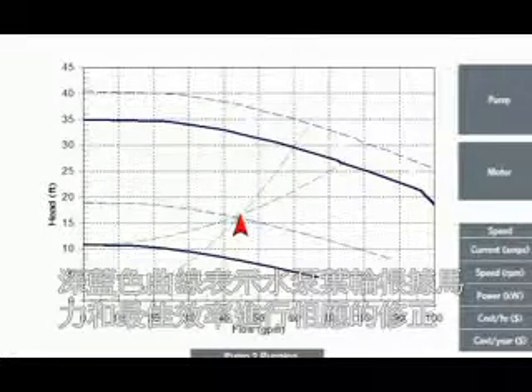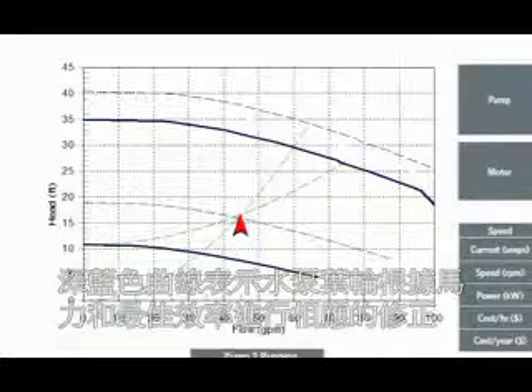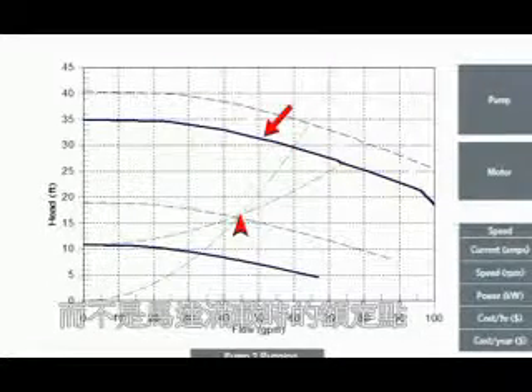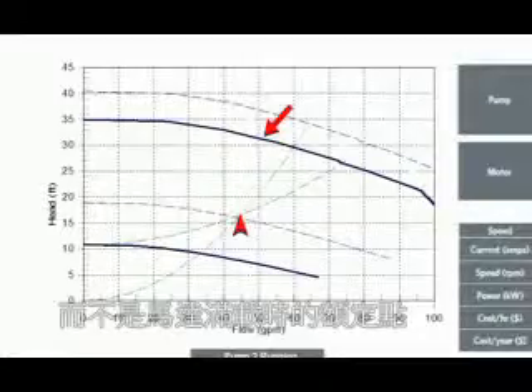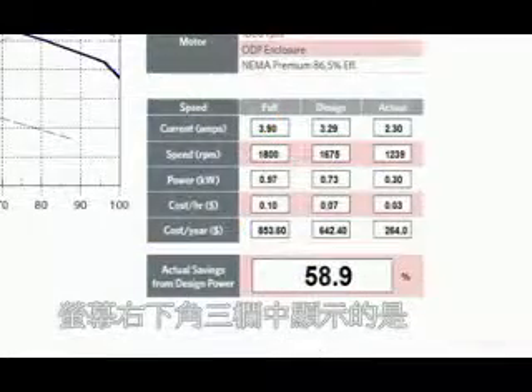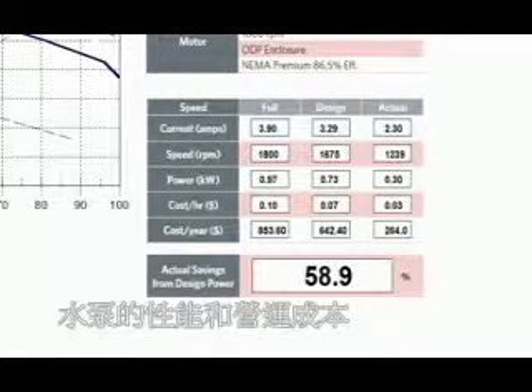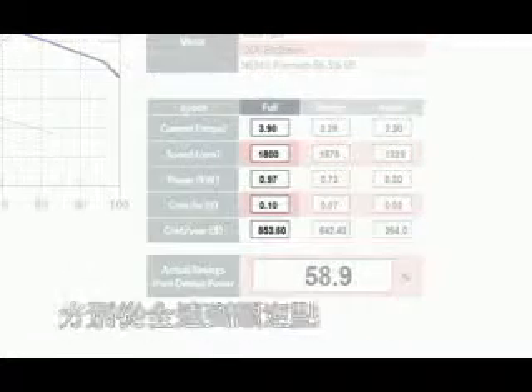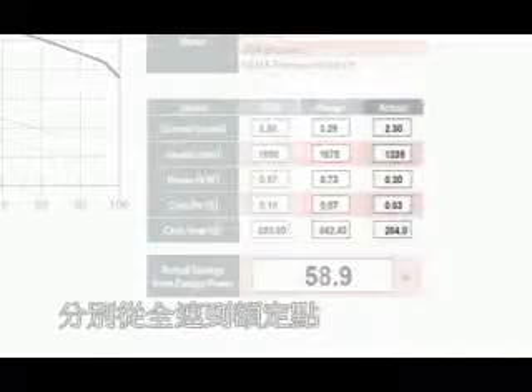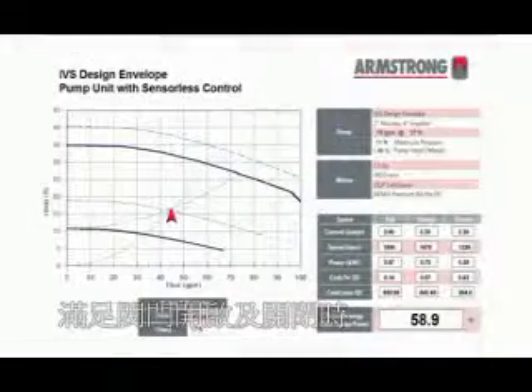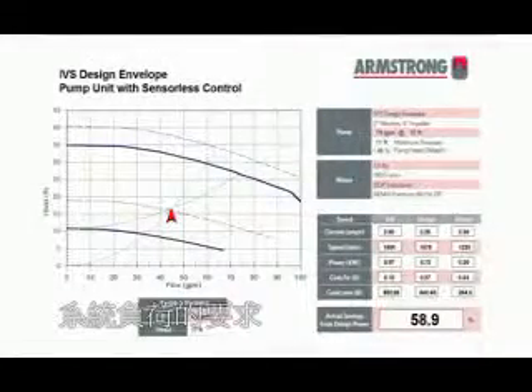The impeller is trimmed to the motor power and pump best efficiency point instead of the duty point for full capability of the installed motor. The design speed of the pump in the system is shown in solid blue. The three columns at the bottom right of the screen display the pump performance and its operating costs by going from full speed setting to design point to actual pump performance in order to satisfy the system load as the valves open and close in a system.